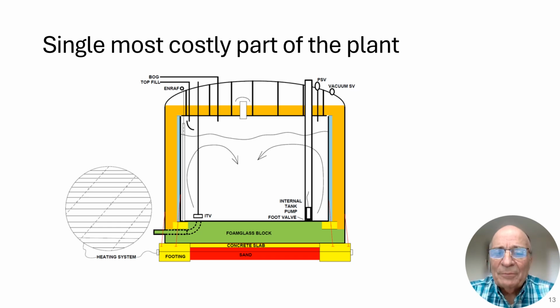Before leaving the topic of pumps, I want to touch upon the different types of pumps and the different configurations. Many of the newer tanks, in fact, most of the newer tanks, have no bottom penetration, and the pumps are inside tubes so that the pumps are submerged 100% of the time. So you might have four tubes with three pumps, with three of the tubes having pumps, and the fourth is just a spare tube, but you have three different pumps available for use. The key with this is that these pumps are always submerged in the LNG, and they're always ready for operation.